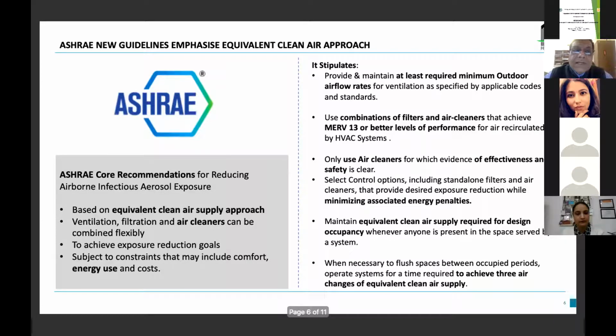And just for information's sake, this guide's core recommendations stipulate that at least the required minimum outdoor airflow rate should be provided and maintained as specified by applicable codes and standards. This can be achieved by a combination of filters and air cleaners to achieve MERV 13 filtration level or better. And these air cleaners are going to play a major role, but we have to take care that the solution we develop is not a burden on the energy consumption, but minimizes the associated energy penalties.